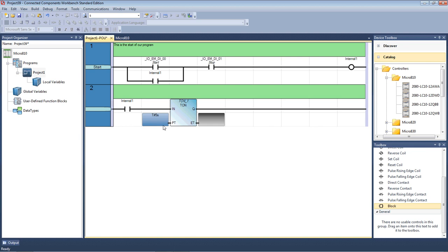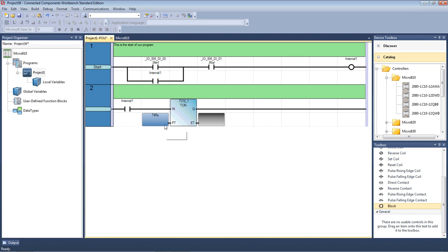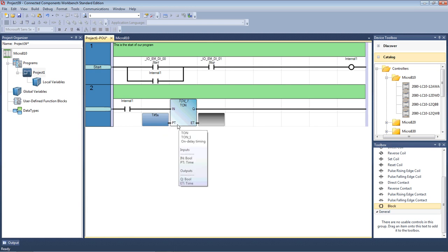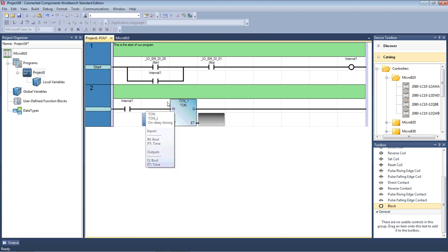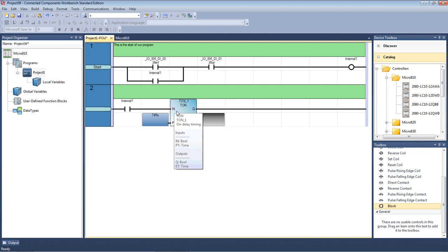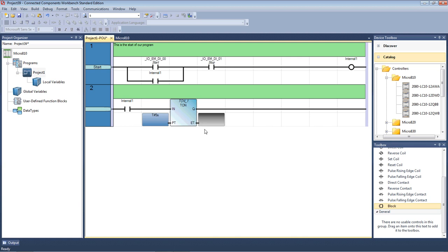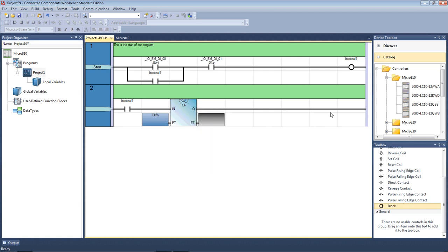If you notice there's a little exclamation mark down in the right-hand corner of the box here, until you actually put your address the block. And that tells you that it needs something in that block, otherwise it's faulty. So that's our predetermined time. So that'll run, that means this timer, when this closes, that'll run for five seconds. So the elapsed time will show the elapsed time. It'll count that five seconds out. And then it'll turn this Q, which is the output of this timer, it'll turn that on.